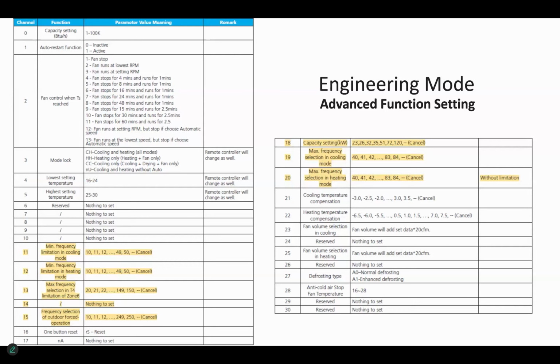Enhanced defrosting: you can either set it from engineering mode or with the dip switch out here. Let's do the dip switch, which is much simpler. Engineering mode is a pain in the ass, but it's a pain on purpose. They don't want every Tom, Dick, and Harry getting in there and messing with the parameters. We'll produce a little tech tip sheet with our recommendations.